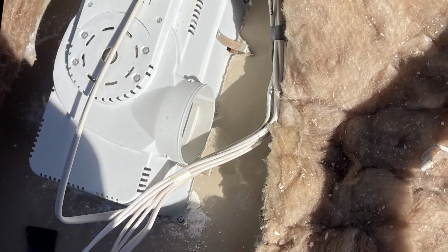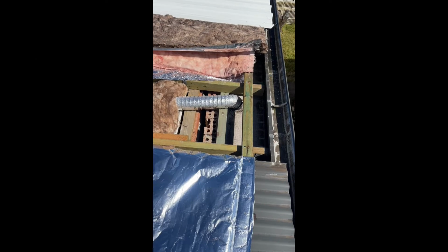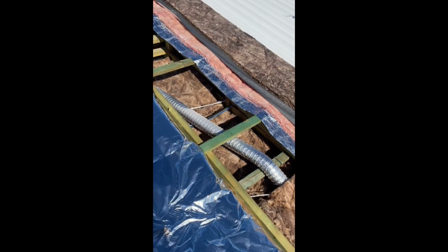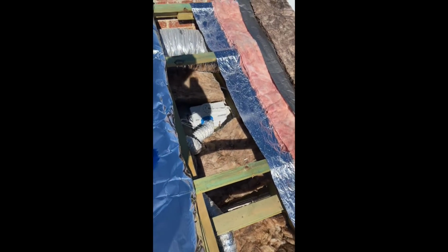So we see this quite often where ducts that are meant to be connected to exhaust fans aren't even connected at all, simply because the tradesmen who are installing the systems have no idea as to the importance of properly ventilating bathrooms and the like.